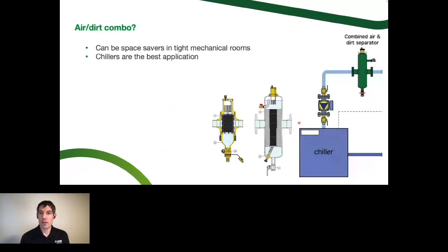This one I see quite a bit in pictures that people think, oh, I can get an air and dirt combo separator and it's going to save some money. The problem is air and dirt combo separators are really for chiller applications, because at this point in a chilled water system, the hottest water where we can separate the air and the dirtiest water coming back from the return are in the same spot. In a heating system, they're in opposite spots. So the dirtiest water is on the return, the hottest water is on the supply. In a chiller system, this is a great device to use because they're in the same spot.